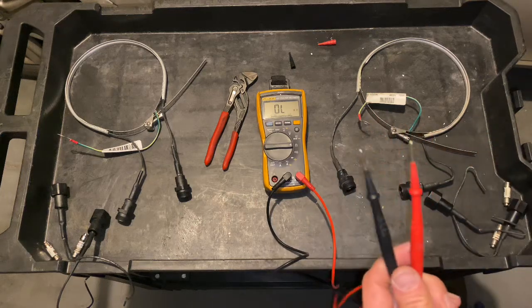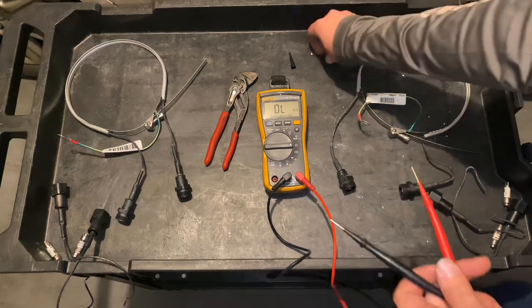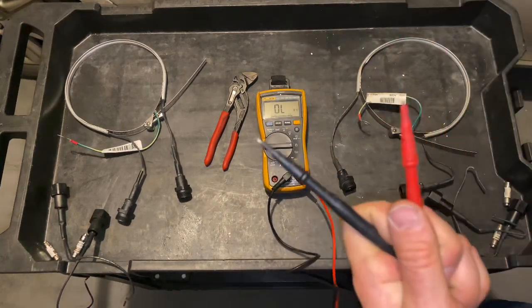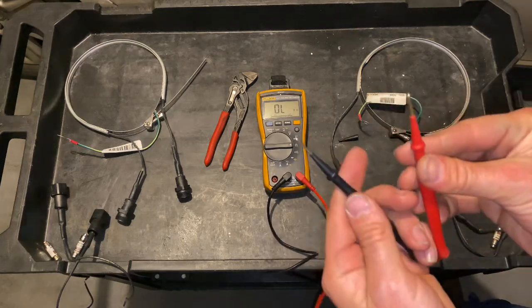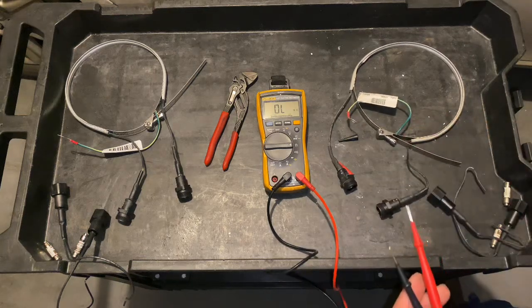Another thing that I've had happen a few times is I thought crankcase heaters failed checking with my guards on, on my leads because I wasn't making a good electrical connection. So make sure you got your guards off when you are checking these crankcase heaters.